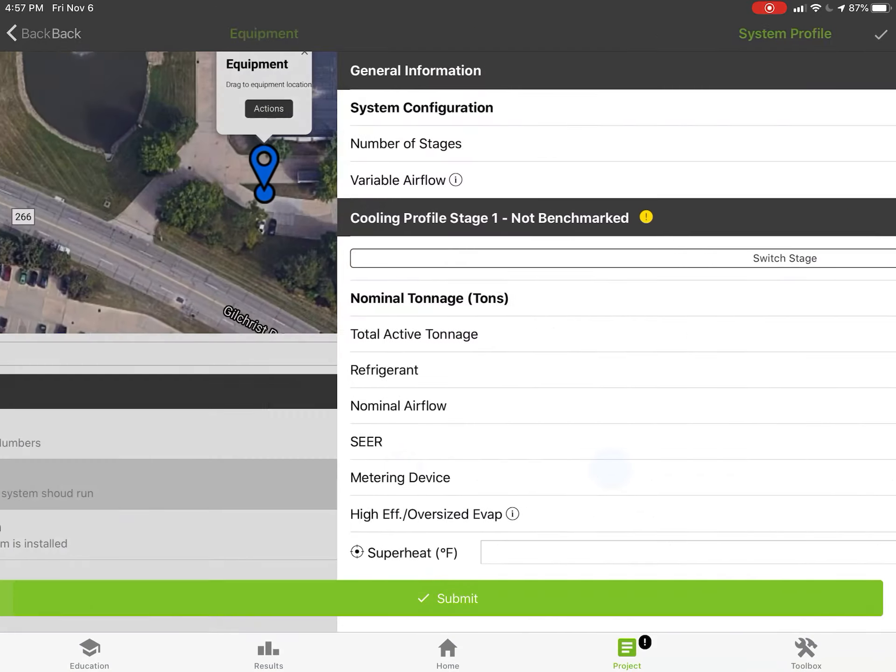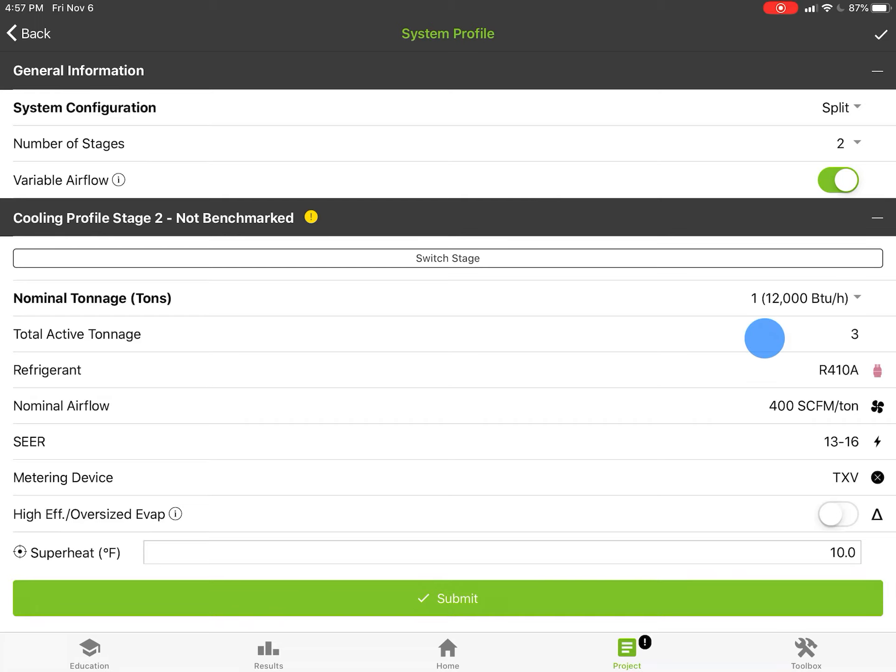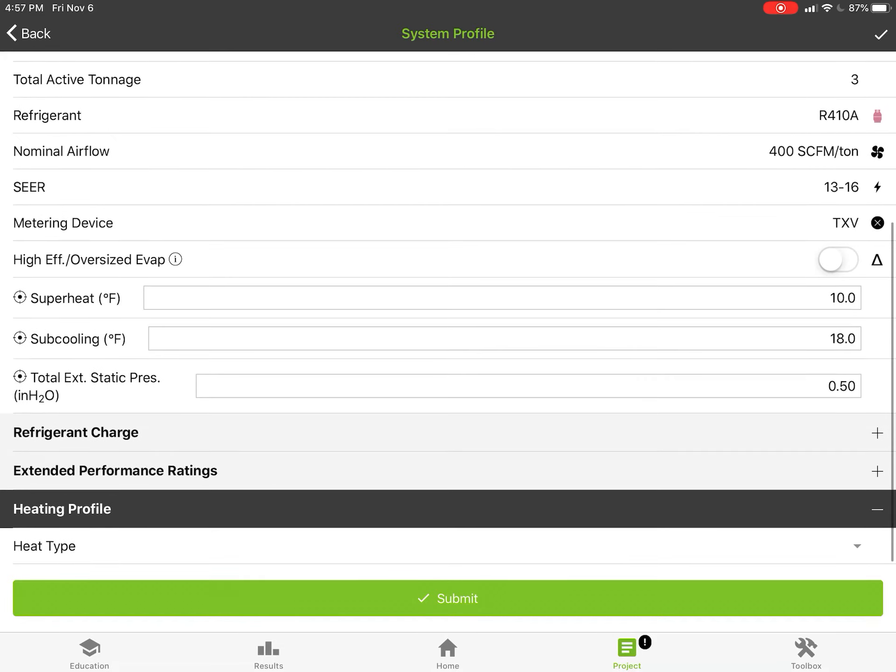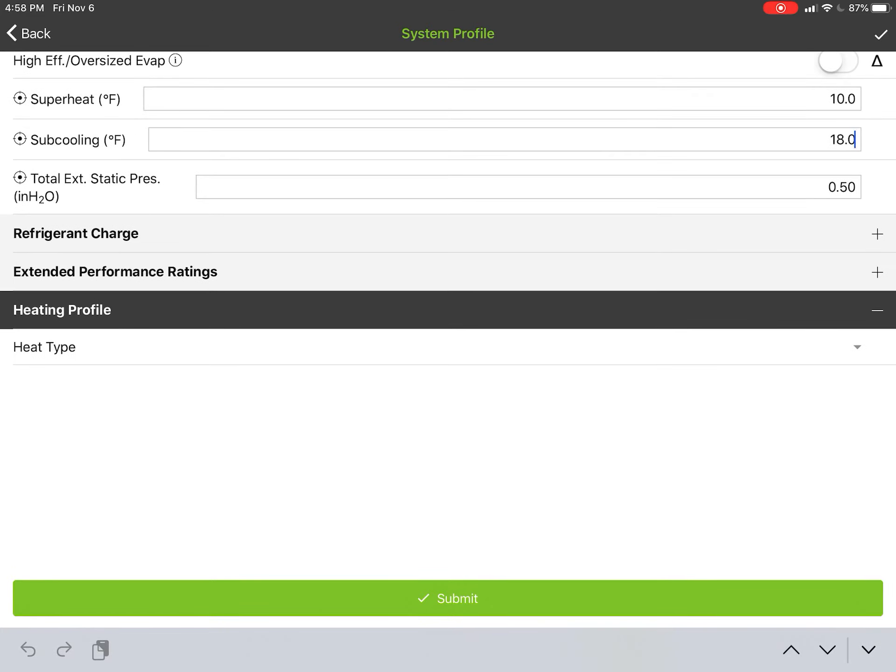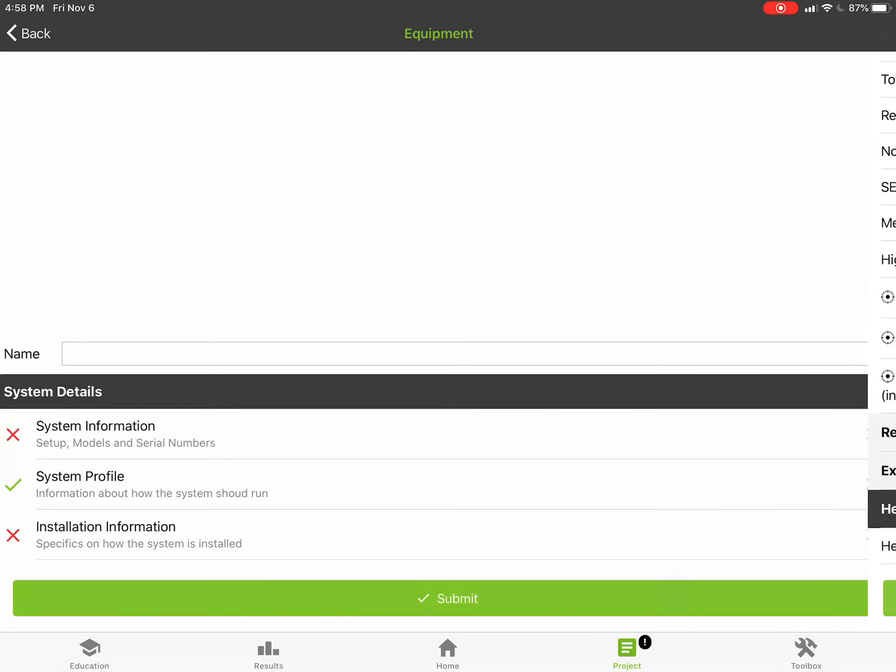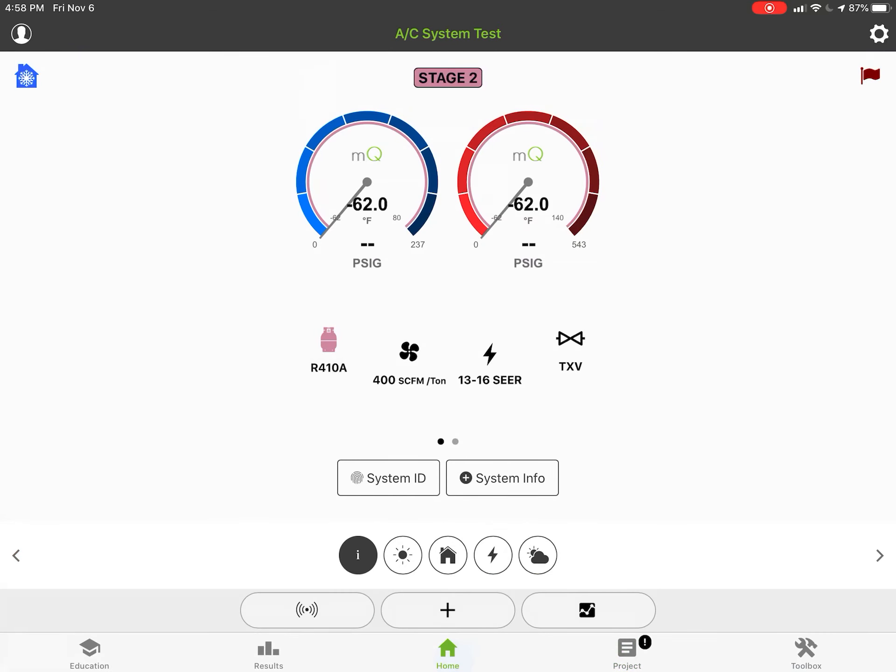Now I'm gonna switch stages here and now automatically it carries it over assuming you're gonna be a two by two, but I'm gonna make this a two by one because that's what I have. You notice that went down. Now total active tonnage is three, so when I'm on second stage I'm gonna take my two tons in first stage and add in my one ton, total tonnage of three tons. It's gonna carry over my targets subcooling which I can change if I have a separate subcooling, like maybe it's 16 degrees or so on second stage. I'll just hit the submit key and carry that across.